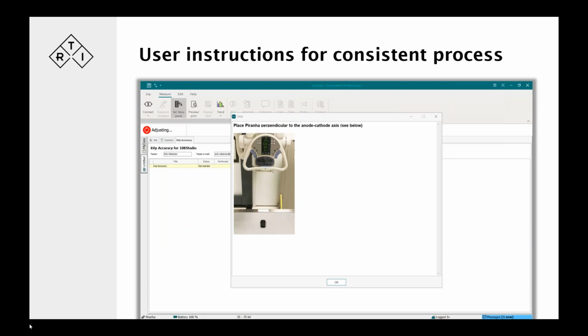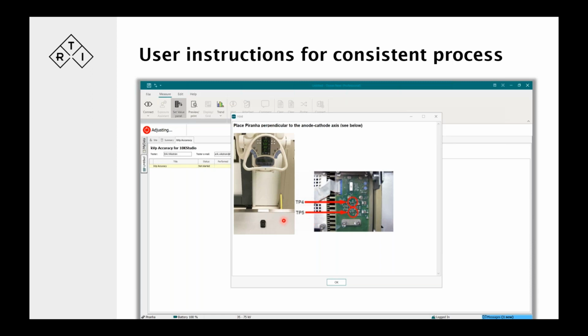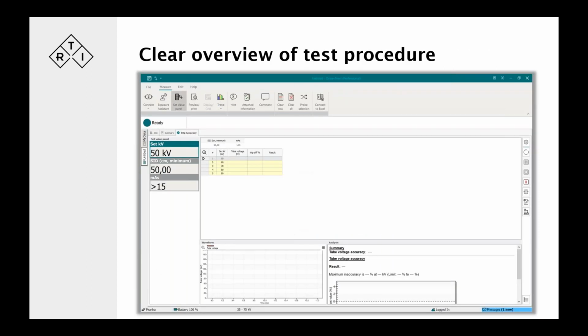As it opens up, we have a prompt, or can have a prompt, if you like, to give instructions to place the Piranha perpendicular like this with an image, for instance. Click OK to advance beyond that and to start the actual measurement. And these instructions can be anything. It could be a picture, it could be an instruction like this, where to attach. It could be an excerpt from a PDF file or text, whatever help they would need. Once that's done, it moves in and starts getting ready for the first measurement of a kVp accuracy test.